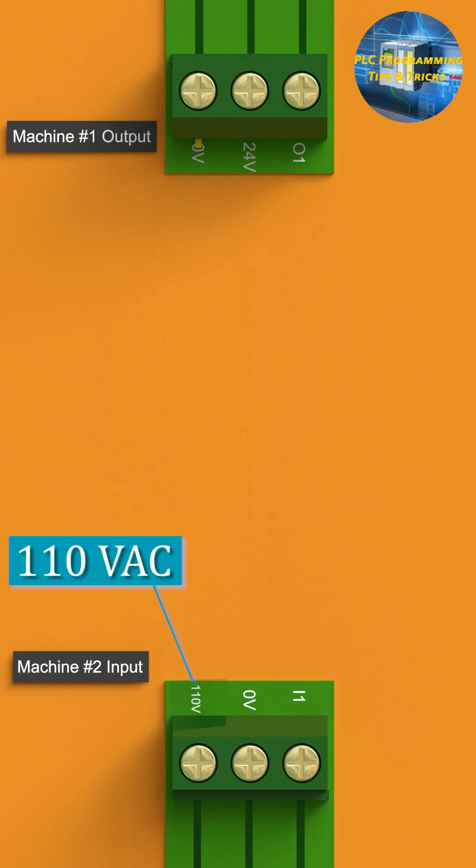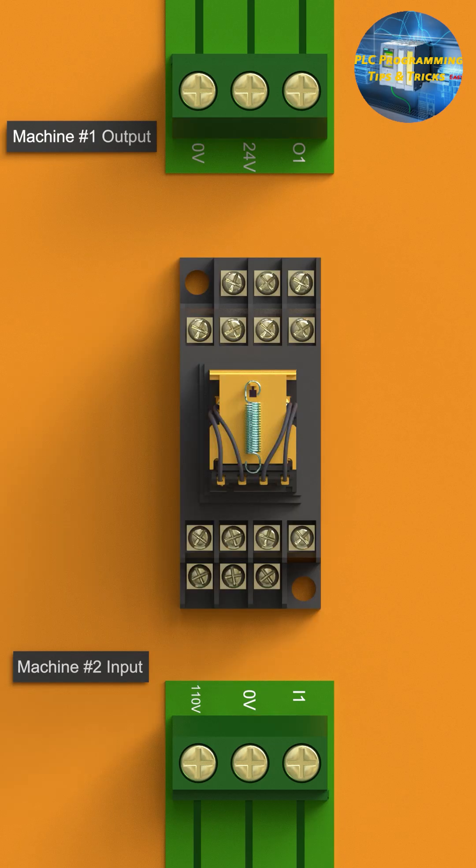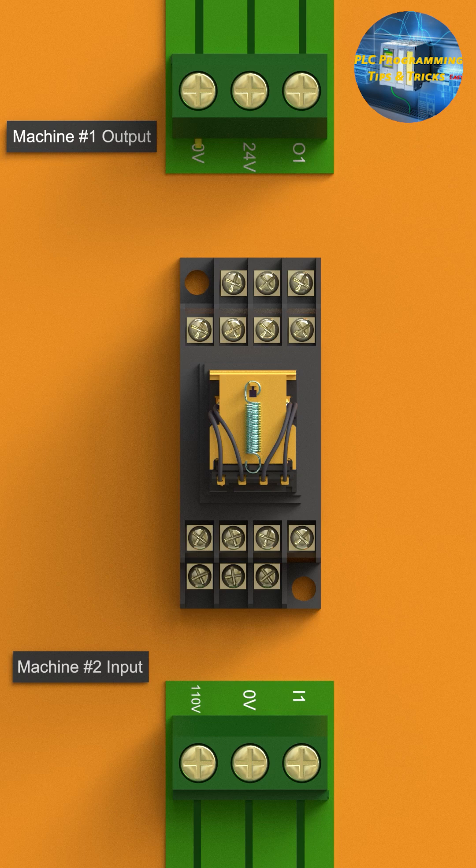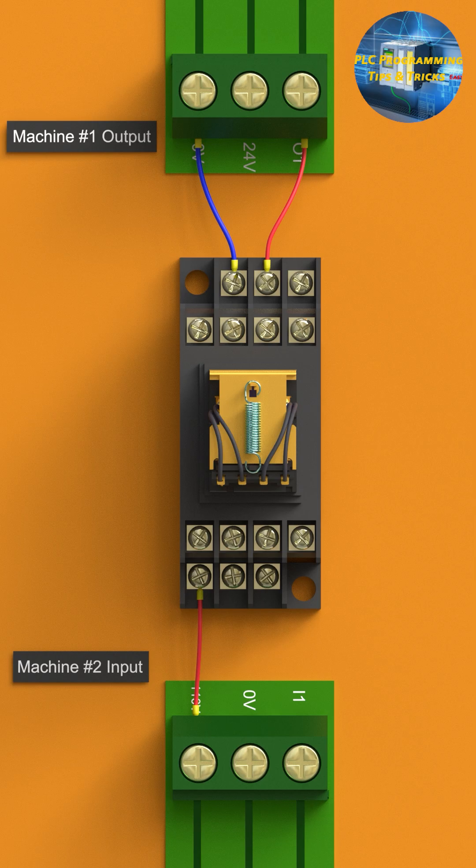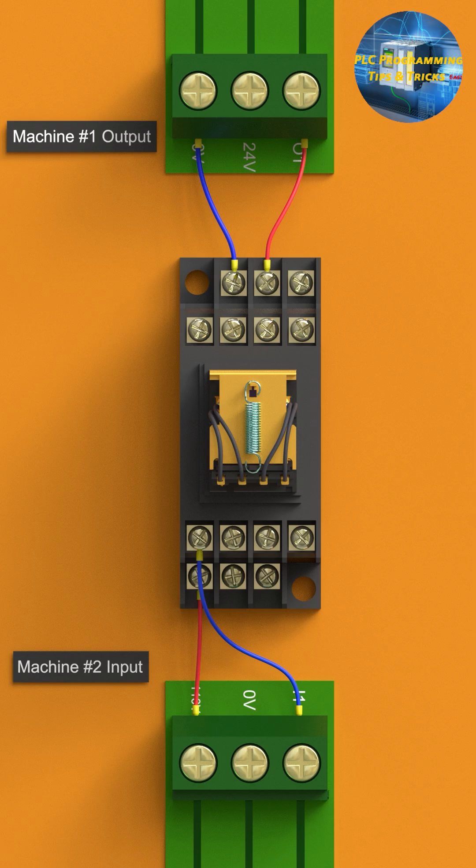Here's where the dry contact concept comes into play. We will simply insert a relay with a 24 volt DC coil in between these machines. Now the output signal from machine 1 turns on the relay coil, and from the normally open dry contact of that relay, 110 volt AC signal goes back to the machine 2 input terminal.